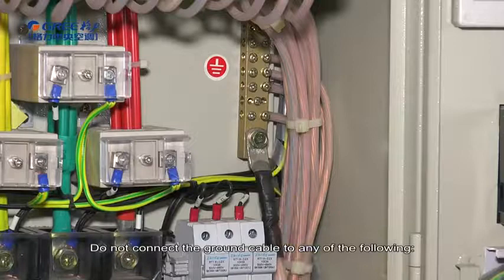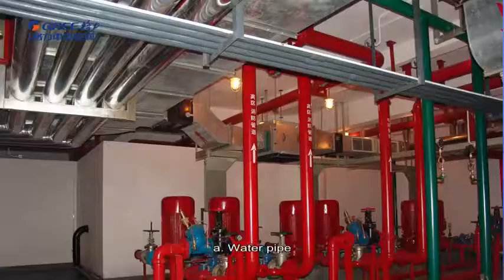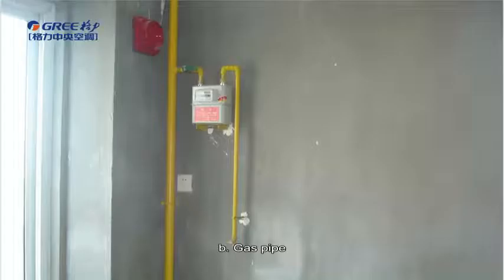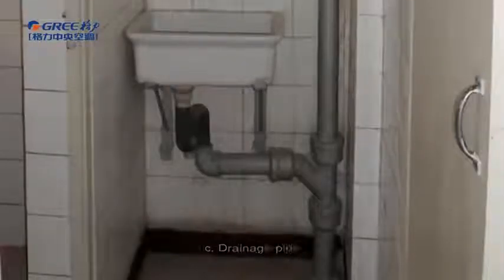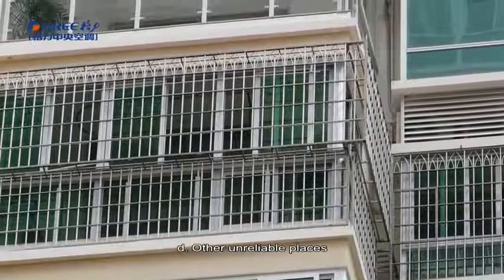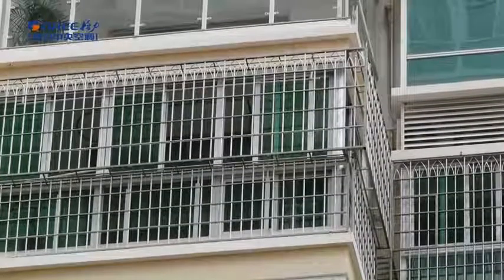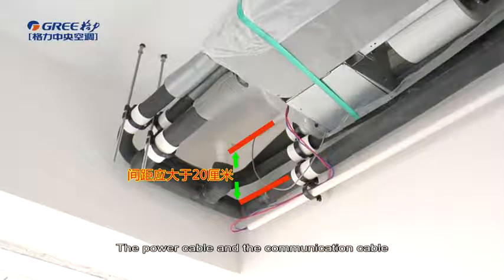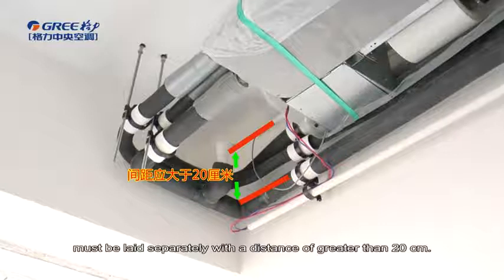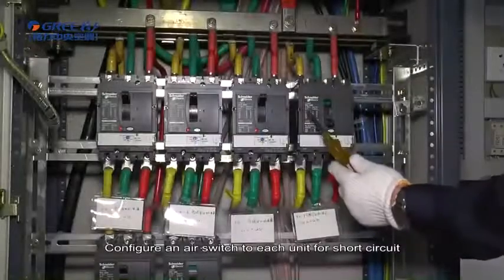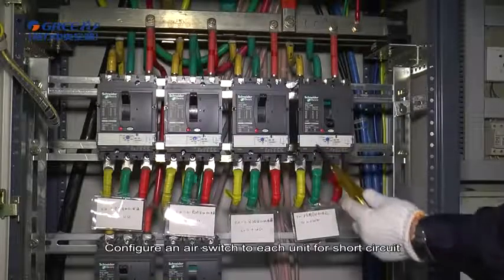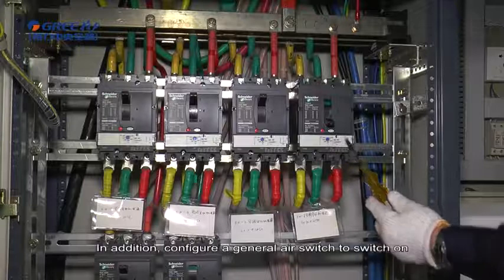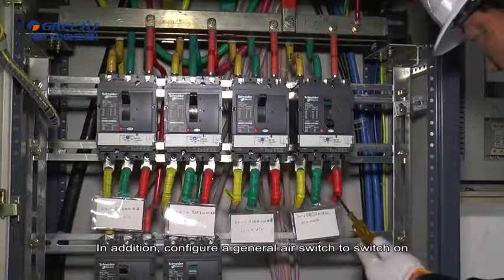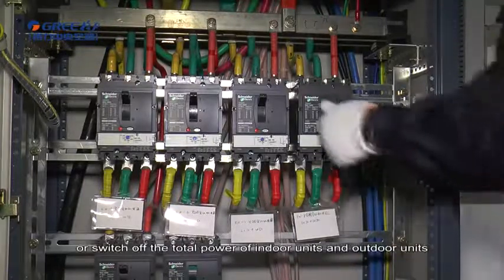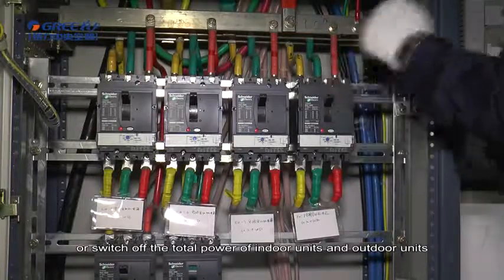Do not connect the ground cable to any of the following: A. Water pipe, B. Gas pipe, C. Drainage pipe, D. Other unreliable places. The power cable and the communication cable must be laid separately with a distance of greater than 20 centimeters. Configure an air switch to each unit for short circuit and overload protection. In addition, configure a general air switch to switch on or switch off the total power of indoor units and outdoor units.